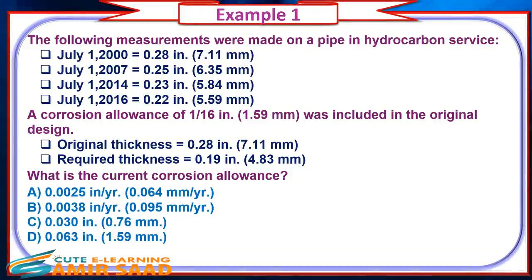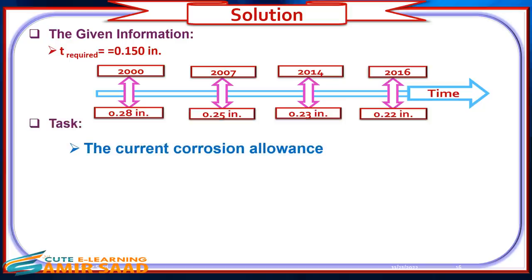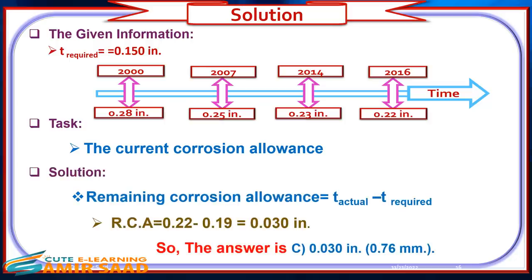Example 1: The following measurements were made on a pipe in hydrocarbon service. A corrosion allowance of 1/16th inch was included in the original design. What is the current corrosion allowance? Solution: Remaining corrosion allowance equals T-actual minus T-required. The answer is C: 0.030 inch.